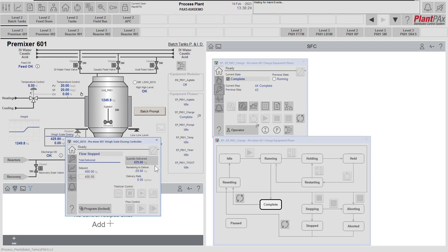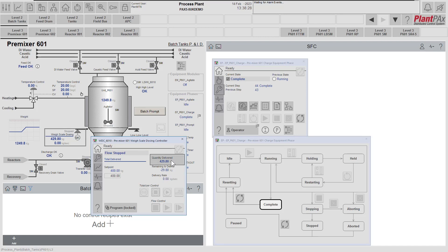There was an overshoot — I deliberately engineered the dosing controller to have an overshoot for demonstration purposes to show this overshoot in reporting. The weigh scale dosing controller does have very sophisticated capability for automatic tuning of dosing and the ability to meet a pre-target and then switch to either a slower dosing or a pulse-testing dosing mode, so you can have very accurate dosing with it if you wish.